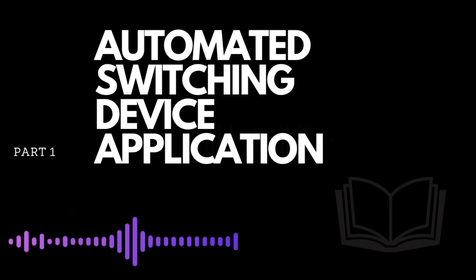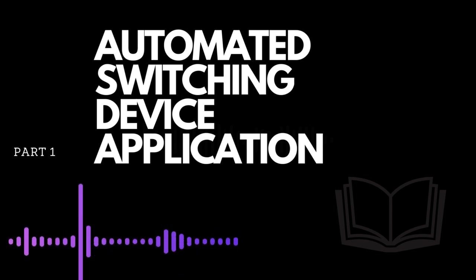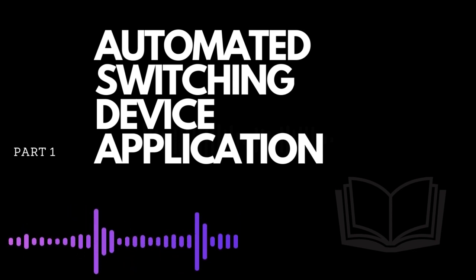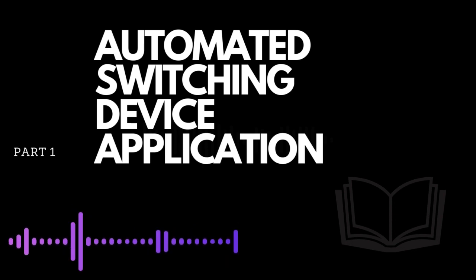The combination of CBs with stable closing and opening characteristics and present-day digital technology has allowed intelligent controlled switching devices to be devised that can be applied to any equipment type. Controlled switching is best implemented with breakers with independent pole operation. 2. Controlled switching basic principles.